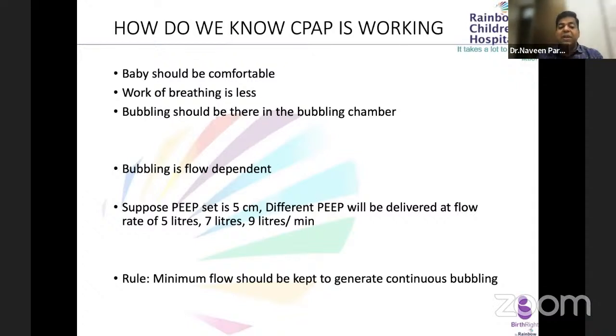Let's assume a situation that PEEP is set at 5. Different PEEP will be delivered if the flow rate is 5, 7 or 9. Let's assume that bubbling is there at 5 also, at 7 also, at 9 also. Then maybe at 5, the delivered PEEP is 5, but at 7, although the set PEEP is 5, the PEEP going to the baby may be 7 or 8. At 9, it may be 8, 9 or 10. So it is always important to look for the bubbling.